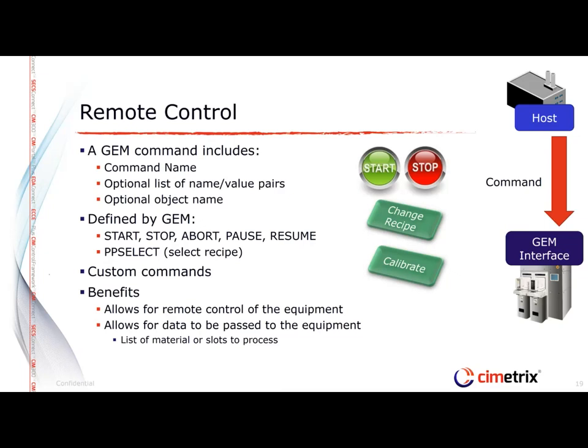There are a lot of features around remote control. Basically, in GEM a remote command has a name, and optionally each available command can also have a list of name-value pairs, so that when the factory sends a remote command to the equipment's GEM interface, each remote command can have data, which allows for excellent control of the equipment and a lot of flexibility.